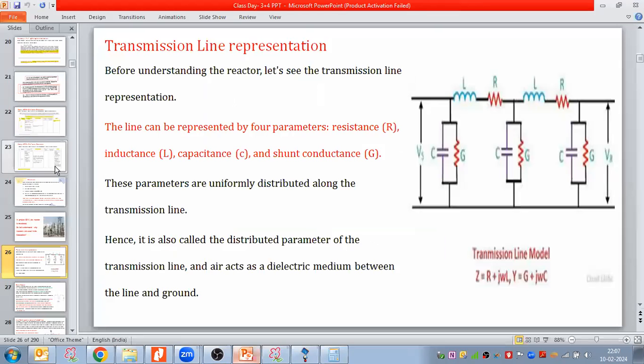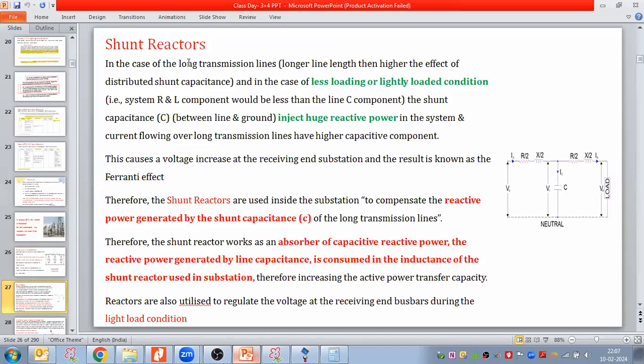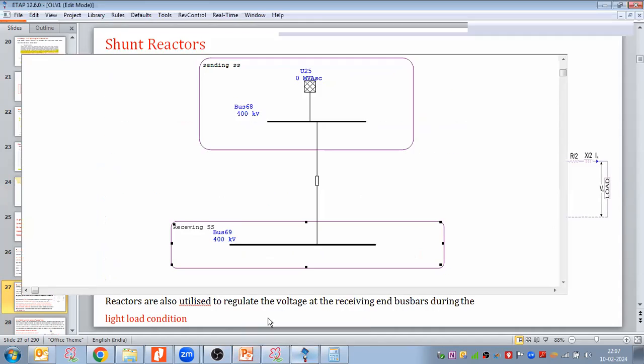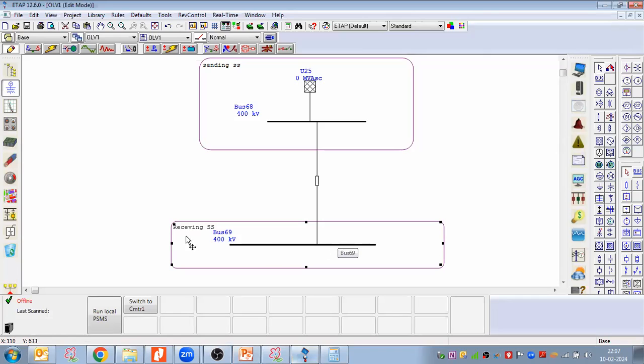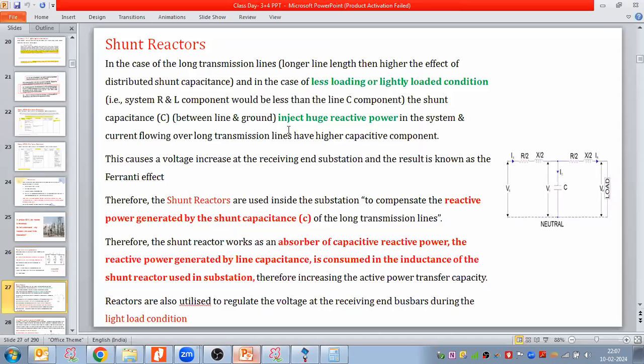As I told you, in case of a long transmission line, which I took as 350 kilometers, the effect of distributed capacitance is higher. In case of less loading, I'm not connecting any load here, so the receiving substation is less loaded or unloaded, which is an important light-load condition. The shunt capacitance injects huge reactive power into the system, and current flowing over a long transmission line has higher capacitive components. This causes a voltage increase at the receiving end substation, a result known as the Ferranti effect.